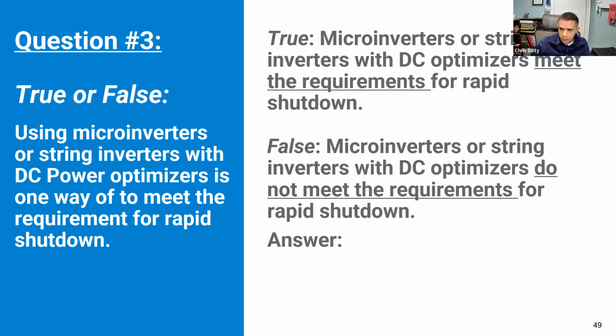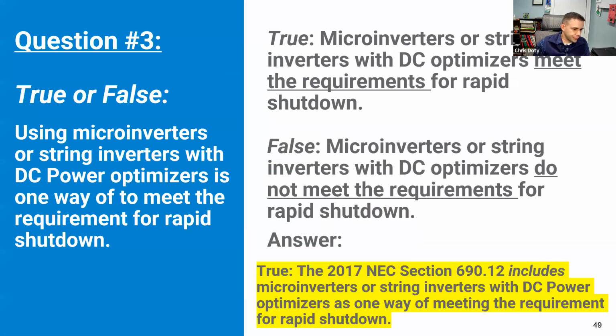So I think the answer to that is true. Microinverters or DC optimizers used in conjunction with string inverters, they do have a rapid shutdown feature, and they are a valid way to achieve that requirement in the code.